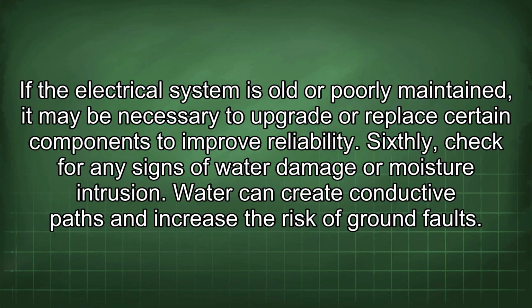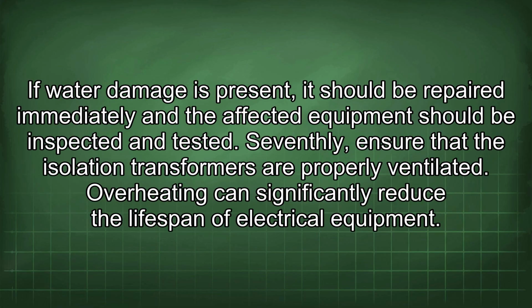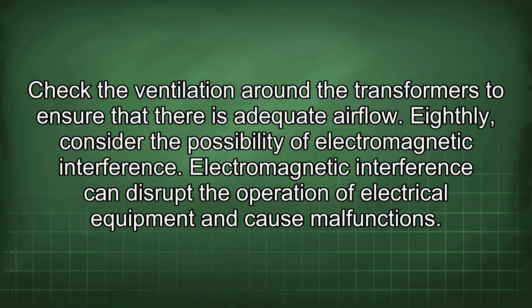Sixthly, check for any signs of water damage or moisture intrusion. Water can create conductive paths and increase the risk of ground faults. If water damage is present, it should be repaired immediately and the affected equipment should be inspected and tested. Seventhly, ensure that the isolation transformers are properly ventilated. Overheating can significantly reduce the lifespan of electrical equipment. Check the ventilation around the transformers to ensure that there is adequate airflow.